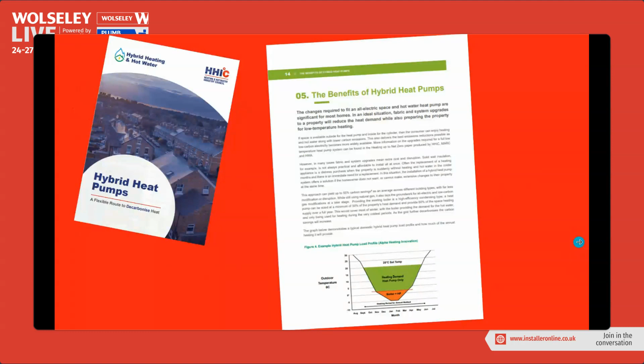I'll just zoom in a little bit on the graph that we've supplied here. I think this is really interesting. So although you've got a gas boiler and a heat pump, it's not 50-50. The heat pump can actually manage a lot of the heating demand of the heating season. You'll see here that for about, I'd say, 60% of the heating season, the heat pump is managing the whole load of the heating. So that's a 60% reduction in gas usage on space heating, which is monumental. It's huge. And when you tag that in with a 20% blend of hydrogen, which we could see this year, it's really interesting how much carbon it can actually reduce.